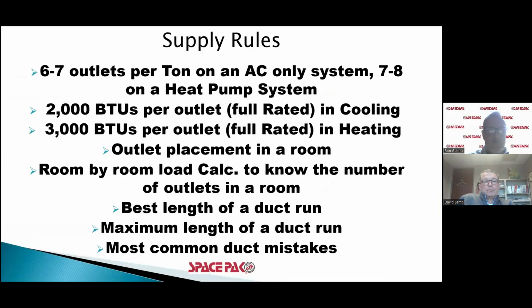All right, so main trunk, 6 to 7 outlets per ton on AC systems only. 6 is going to be noisier. 6 is going to be more often used in a retrofit application. You want 8 on a heat pump system, or as close to 8 as you can get on a heat pump system. You're getting 2,000 BTUs per fully rated outlet in cooling, 3,000 in heating.